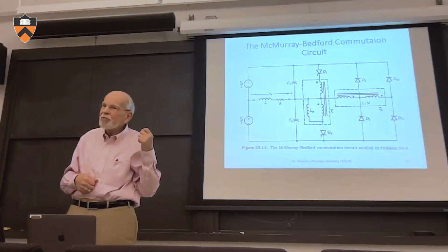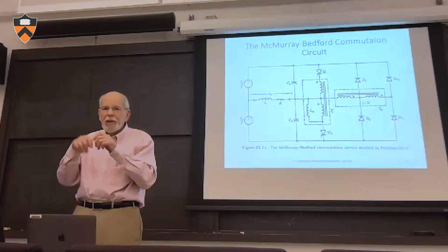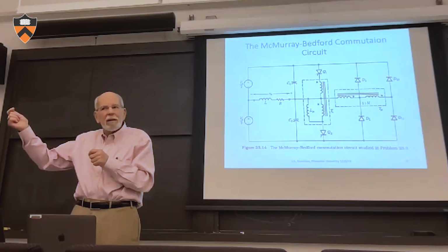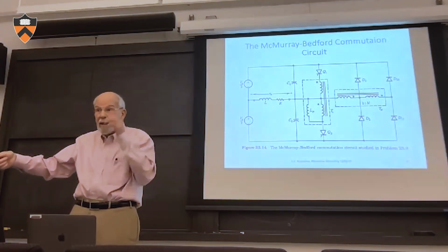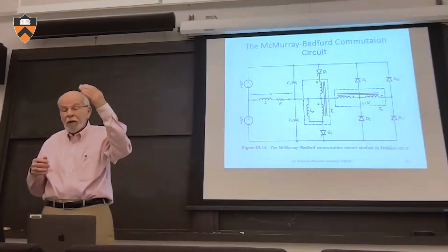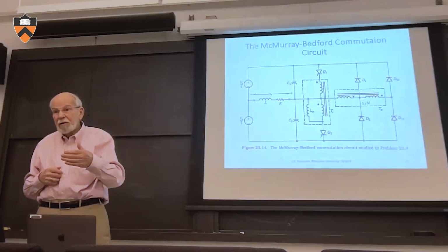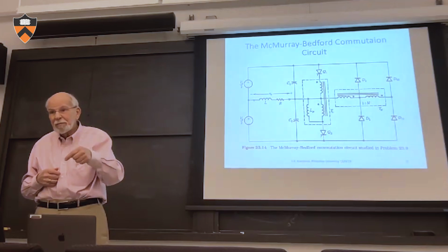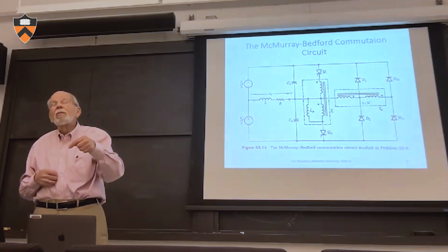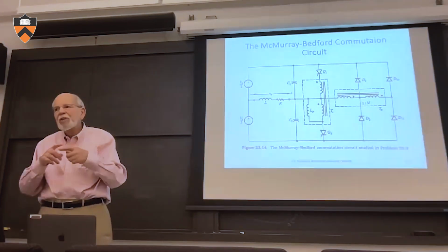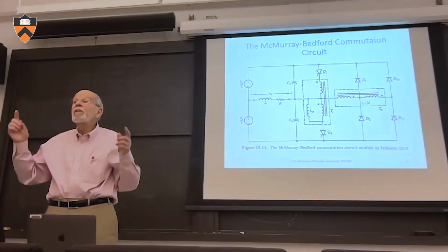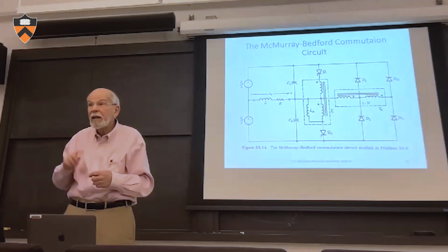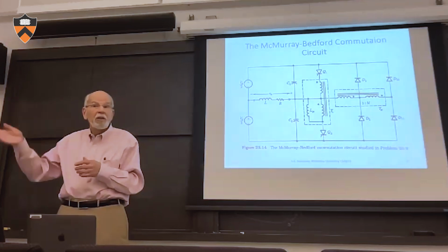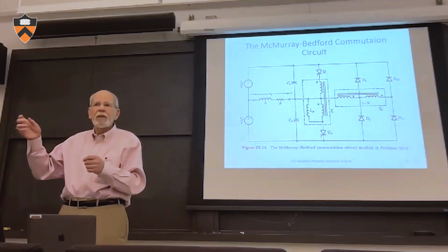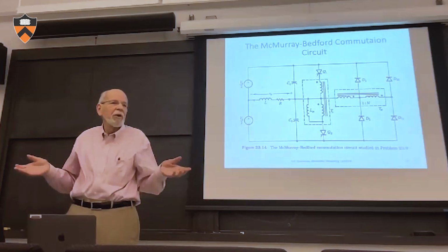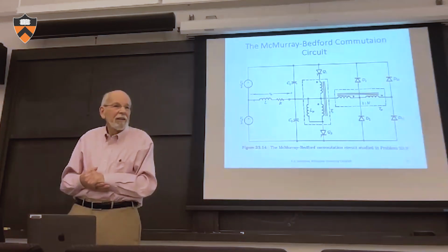What we had in this X-ray machine was a triac which, when they turned it off, there was still current flowing in the leakage inductance. When the triac current went down to the level where it would turn off, there was a huge dV/dt that turned the triac back on again in the other direction. This just continued, turn it off, turn it on, over and over, and the poor kid under the X-ray machine had no clue this was going on.